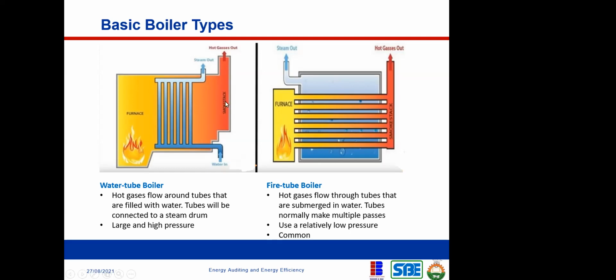Okay, so the difference between the water tube boiler and the fire tube boiler is just the opposite. In this case, notice that water is now in the shell, while the hot gases coming out from the fire pass through the tube. Whereas in the other one, the opposite is the case. Here, water is like in a tank, and you pass hot pipes through the water to extract the heat, and eventually the stack gas goes out from this vent here. Once this hot gas passes through this tube, it deposits its heat into this water, and the water boils and turns to steam, and then the steam goes out from here.